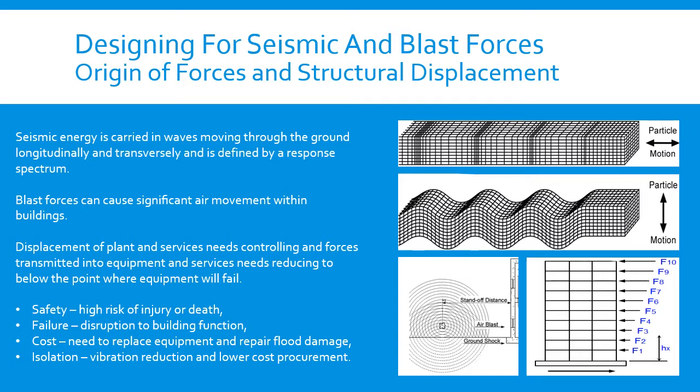A blast is a single displacement of structure that rapidly damps. Seismic events can continue for a period of time, which increases the chance of damage and force amplification. Anchorage of plant, piping and ducting to structure must be done in a way that's considerate to the nature of the equipment and the building in which it is placed.